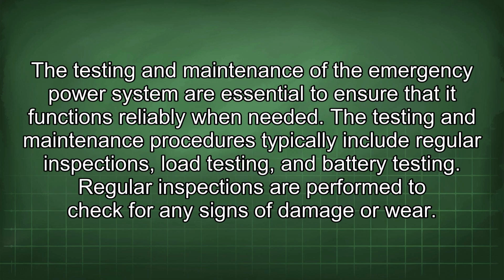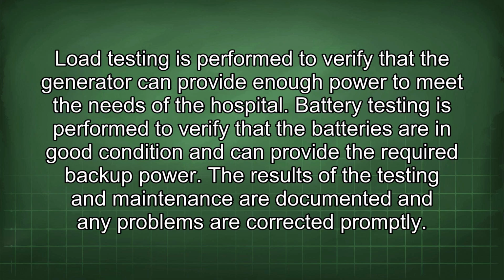The testing and maintenance of the emergency power system are essential to ensure that it functions reliably when needed. The testing and maintenance procedures typically include regular inspections, load testing, and battery testing. Regular inspections are performed to check for any signs of damage or wear. Load testing is performed to verify that the generator can provide enough power to meet the needs of the hospital. Battery testing is performed to verify that the batteries are in good condition and can provide the required backup power. The results of the testing and maintenance are documented and any problems are corrected promptly.